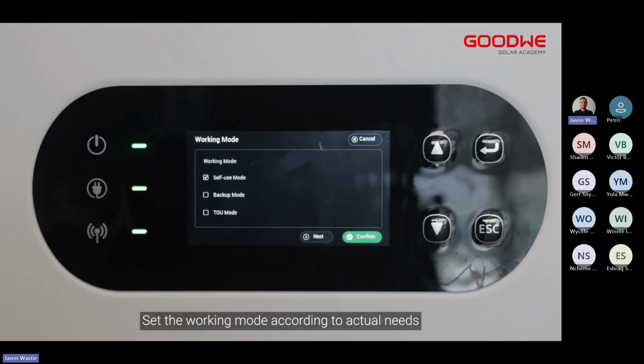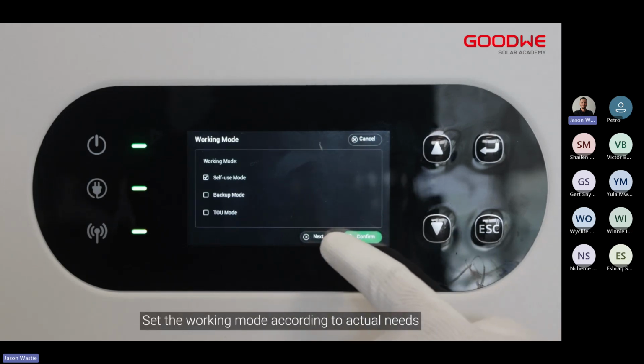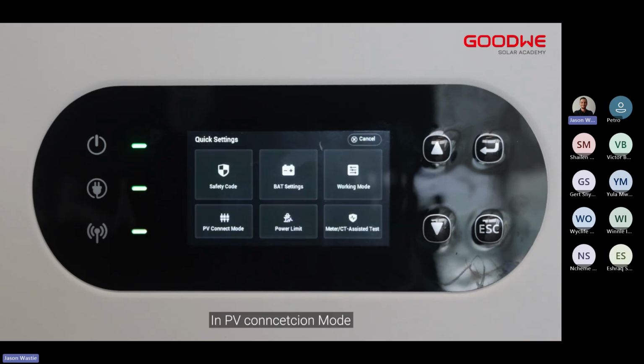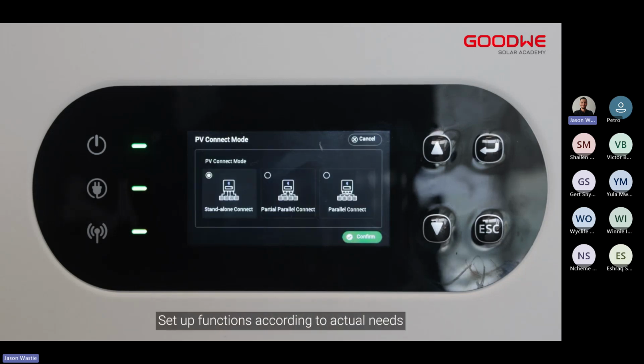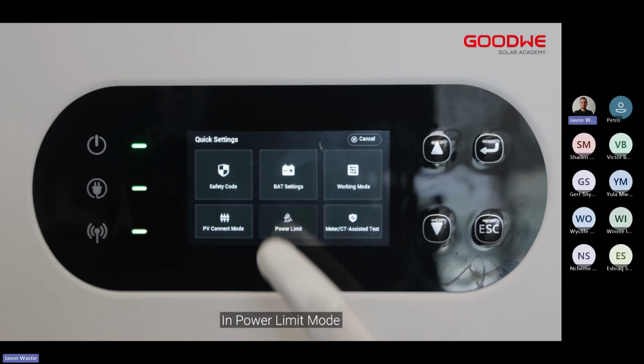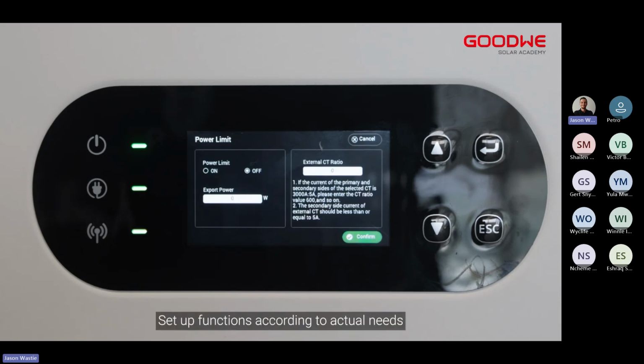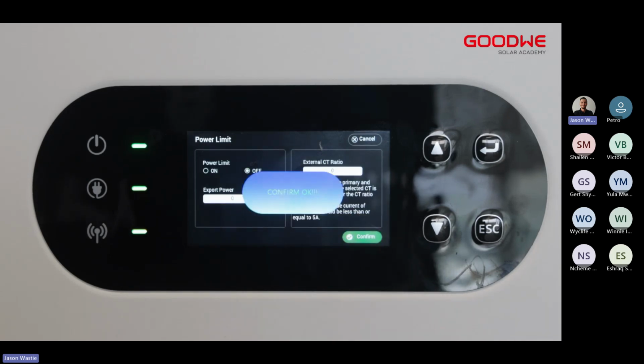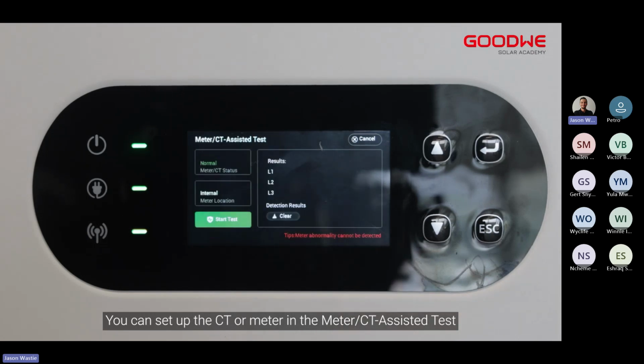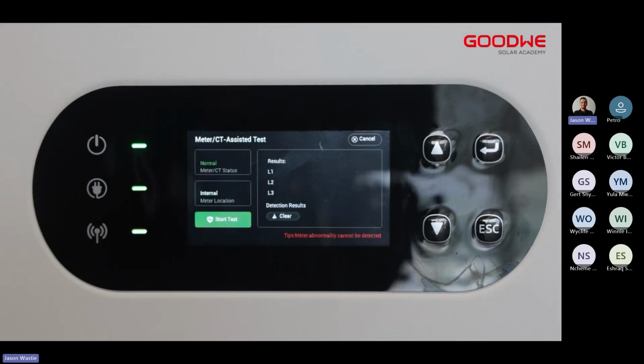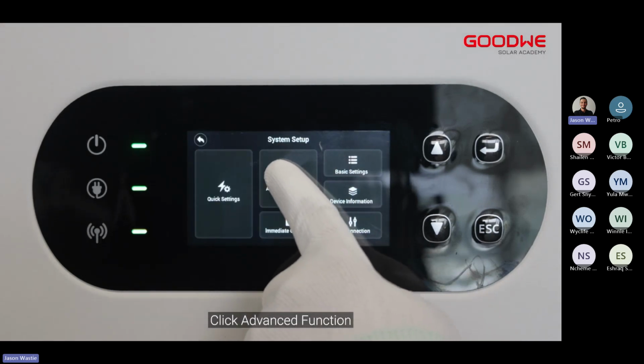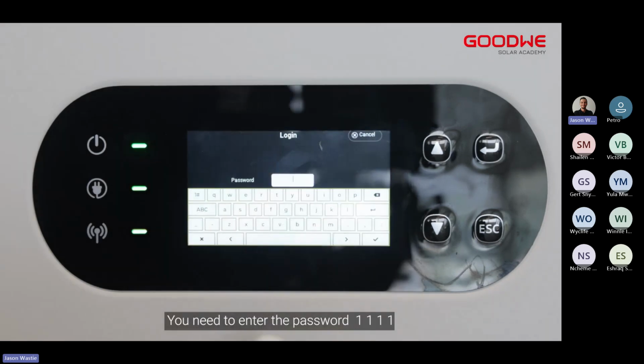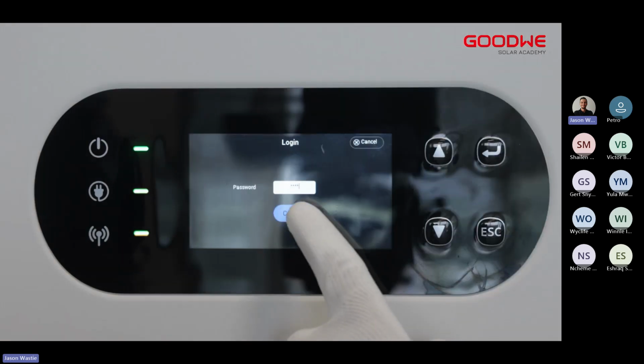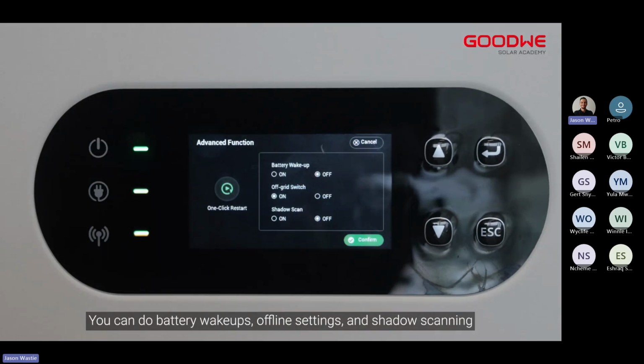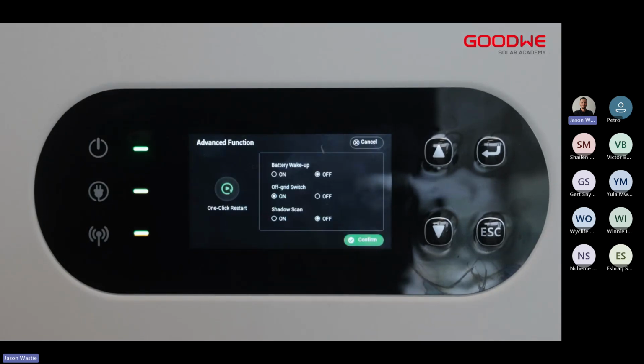In working mode, set the working mode according to actual needs. In PV Connect Mode, set up functions according to actual needs. In power limit mode, set up functions according to actual needs. You can set up the CT or meter in the meter/CT assisted test. Click Advanced Function. You need to enter the password 1111. You can do battery wake-ups, offline settings, and shadow scanning.